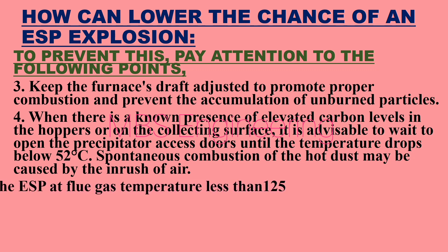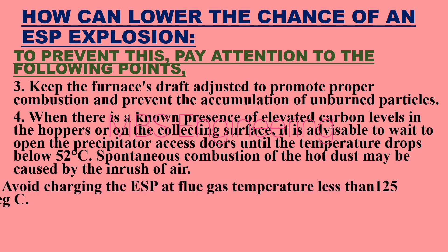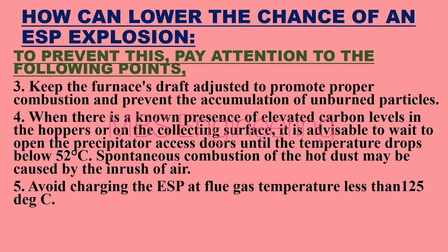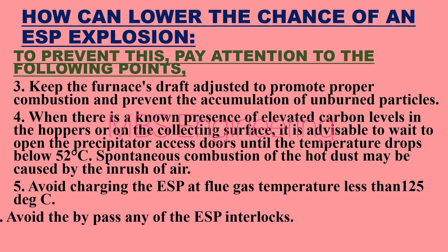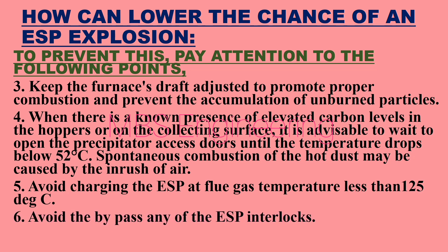Point 5: Avoid charging the ESP at flue gas temperatures of less than 125°C. Point 6: Avoid bypassing any of the ESP interlocks.